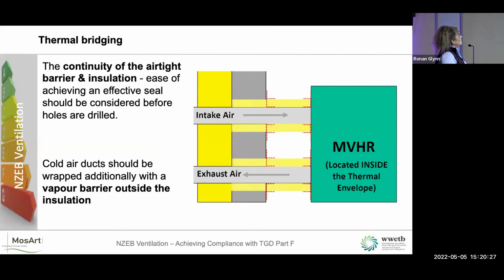So what we do is core out a bigger hole than the duct, fill that with insulation, okay? Take a photograph of it. Then you put your airtight tape on to make it airtight, because we know that vapor is a smaller molecule than air, so the vapor can still get in there. Then we're going to wrap the entire duct with vapor tight insulation as well. And again, we'll put more tape there because a vapor molecule is smaller than an air molecule. And that's the way we do it.